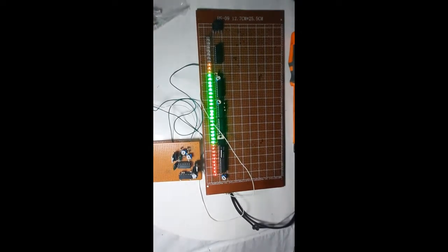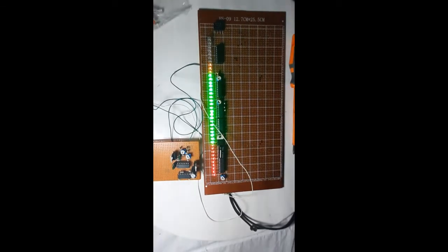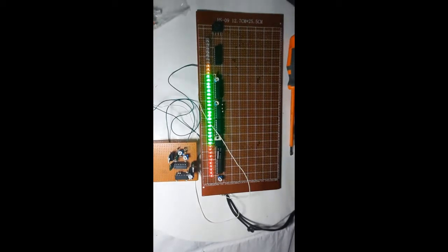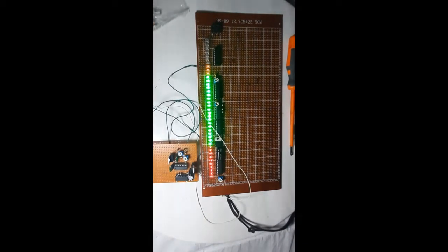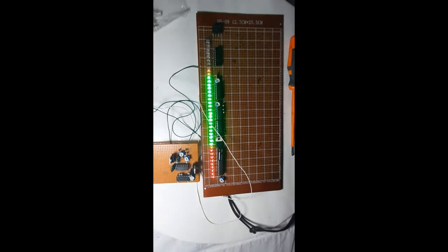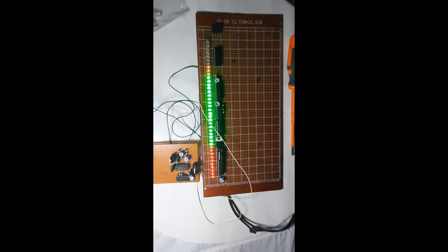But in some cases, if you use a PT100 to measure temperature, we don't have the Wheatstone bridge device at the engine side. In the older system, yes, we used the Wheatstone bridge kept in the control room, but nowadays we don't use that system. So what we do is use a transducer. What does the transducer do? The resistance variation is converted into either voltage variation or current variation.